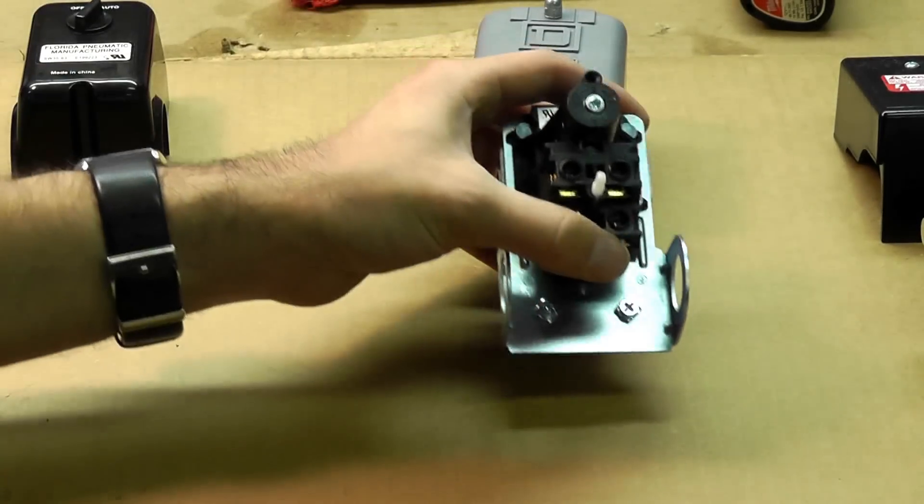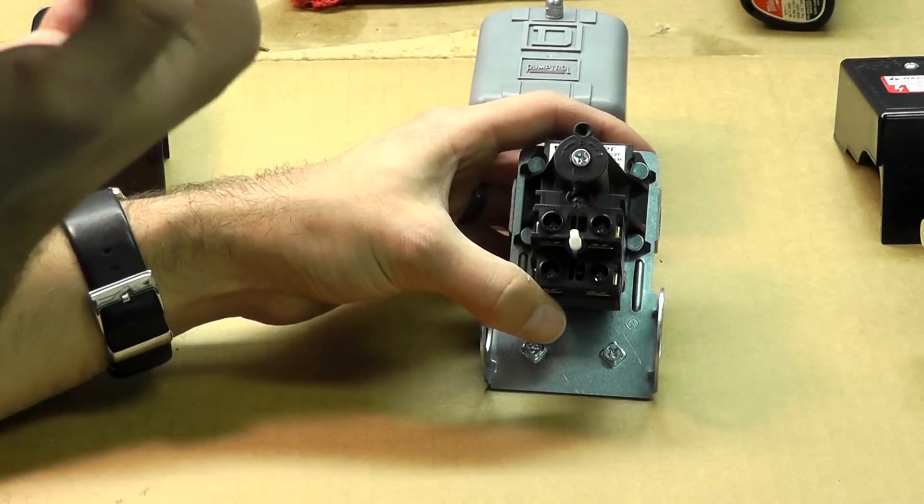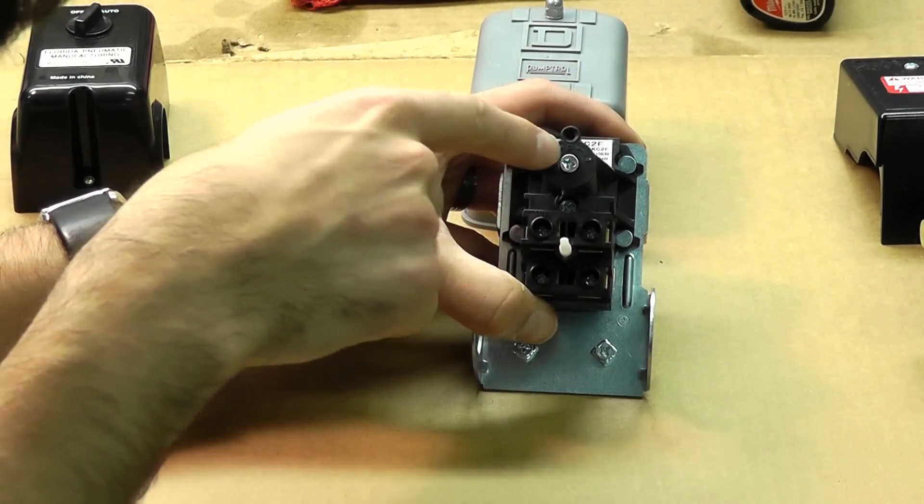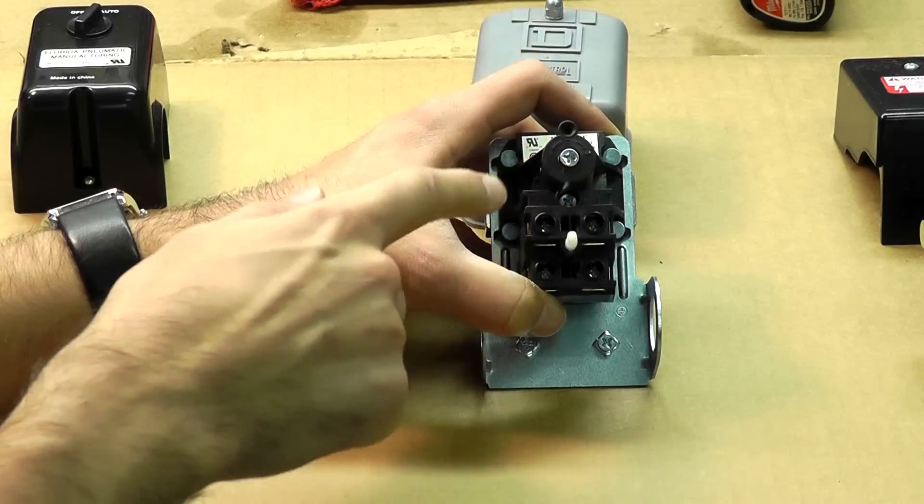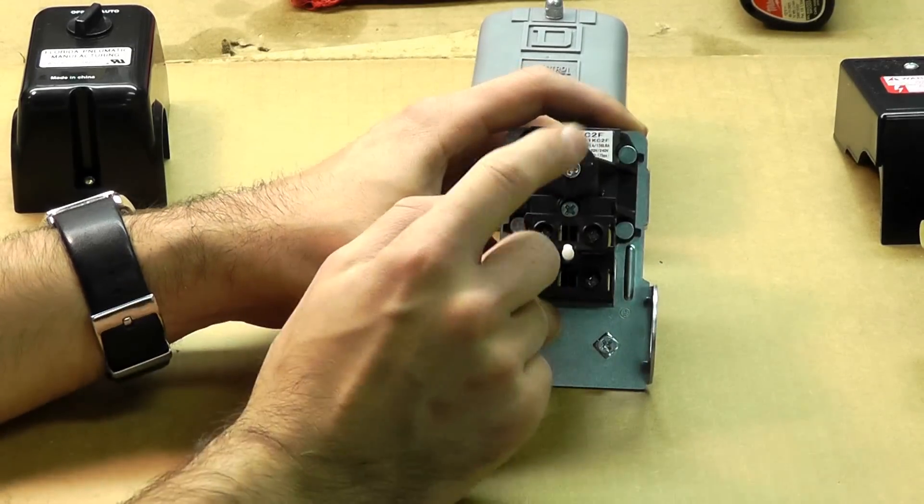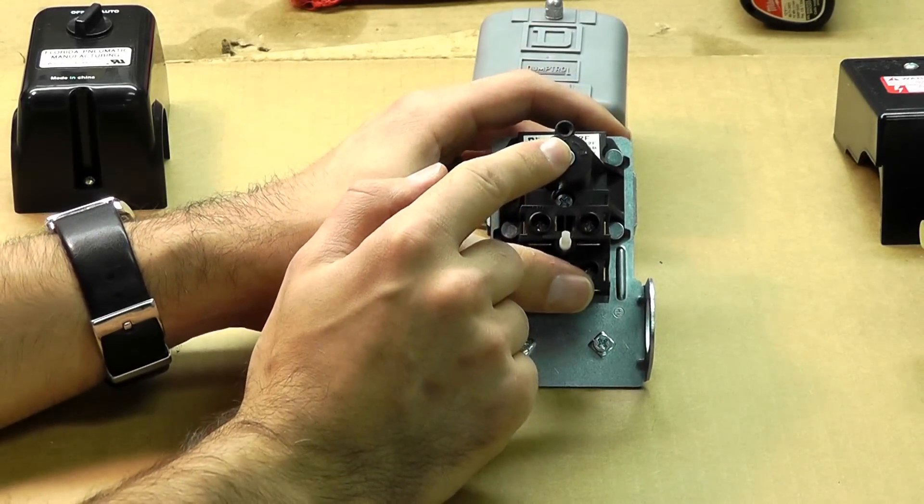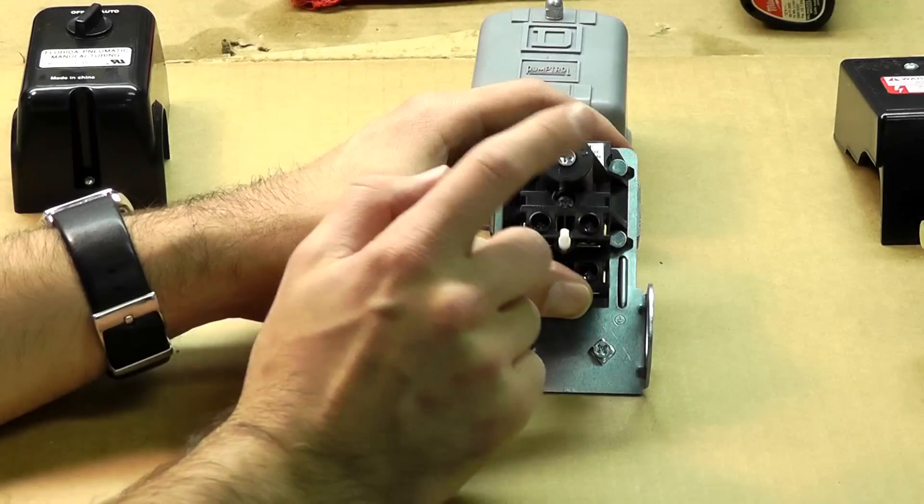And this is a Condor switch, a little bit different. It only has one adjustment. You'll notice this P here, which is pressure of course, and the arrow to the right with a plus and a minus on the left. This just increases the cut-in and cut-out pressure at the same time, simultaneously.